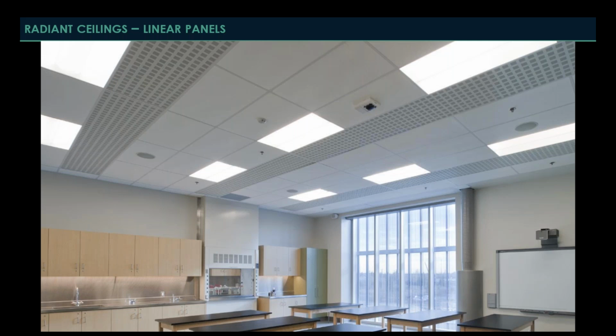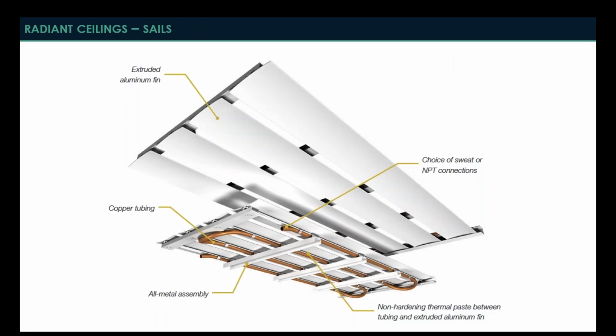And the other unique thing is that with radiant systems, not every panel that gets installed into the ceiling necessarily has to be active. Sometimes architecturally, you may want a look of a very clean linear length, but you don't actually need all of those panels. So the companies offer their panels essentially without the copper tubing attached to the back so that it creates the same appearance but isn't necessarily an active portion.